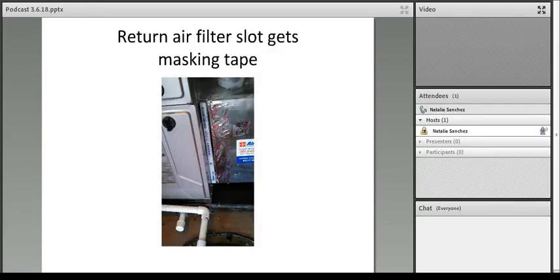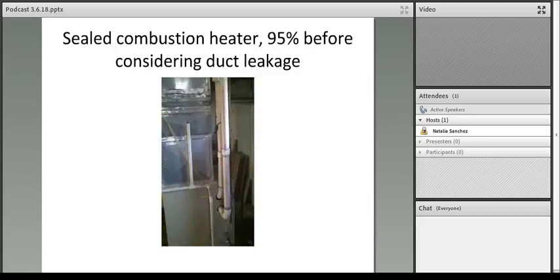And then pay attention to where the air handler filter slot is. Is it covered? Is it airtight? Go buy 3-inch wide masking tape, the cheapest you can find, because you're going to take this off every couple of months to replace the filter and put in a clean one. So you're not going to spend a lot of money on expensive tape here because you're going to damage it frequently. So buy a roll of tape, stick it on this location every time you come to change the filter. Peel off a piece, stick the filter in, stick the tape over it. Now you got it sealed in place.